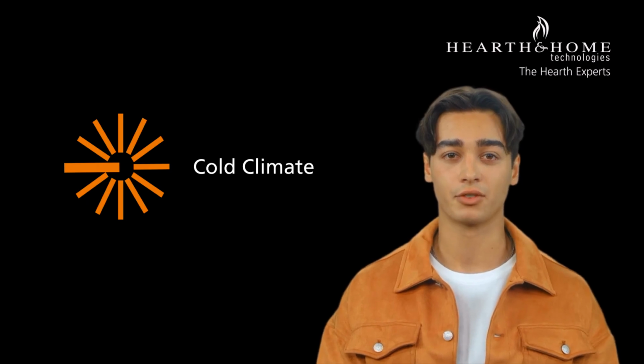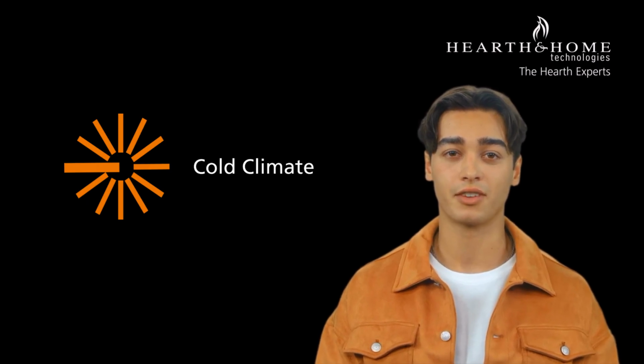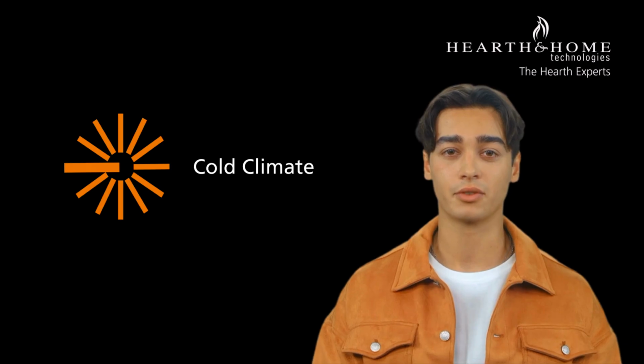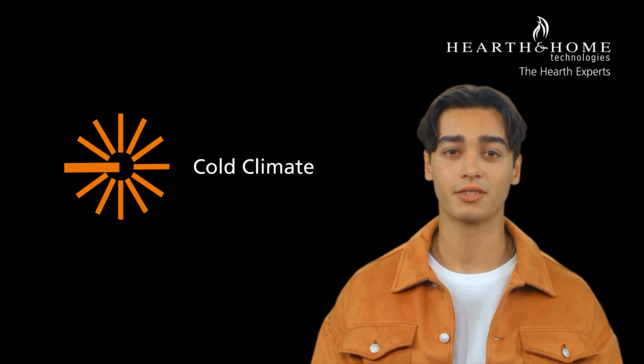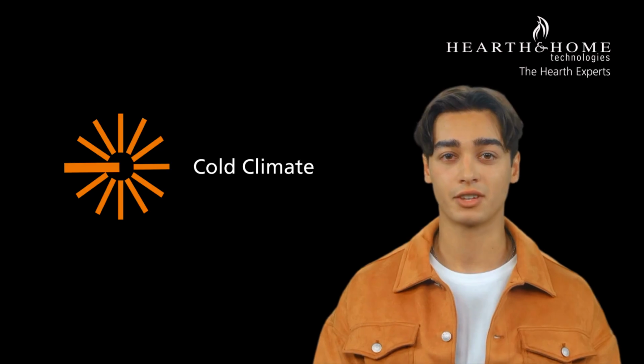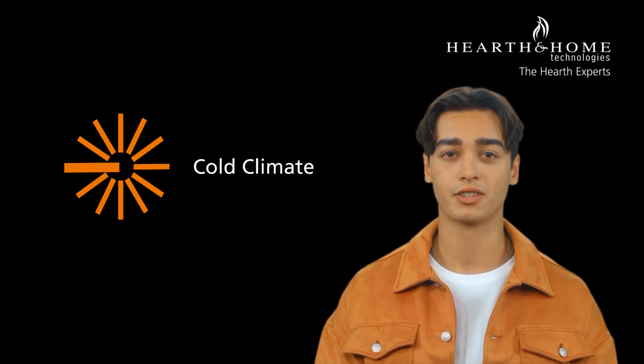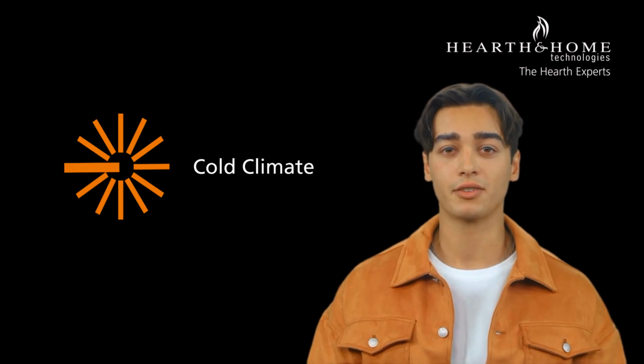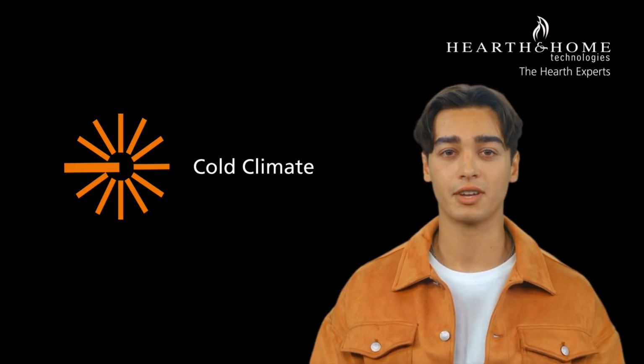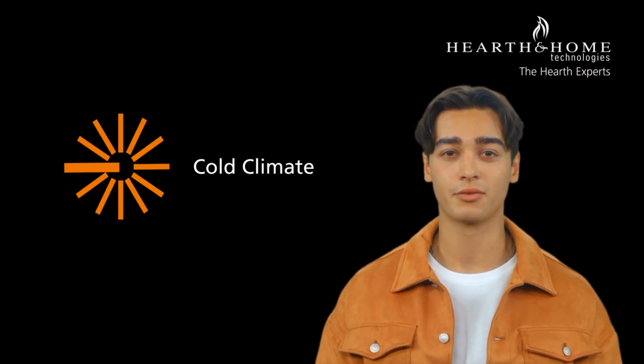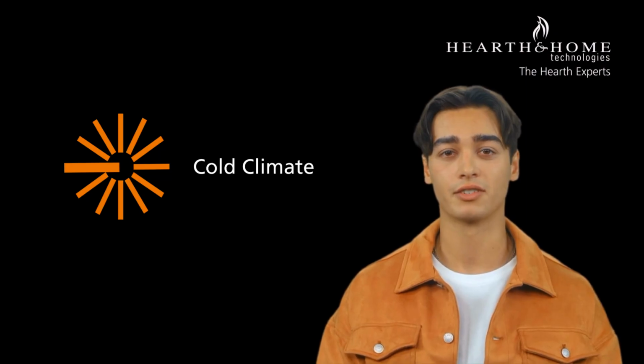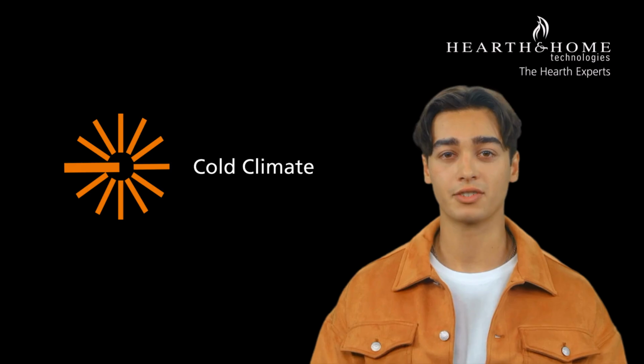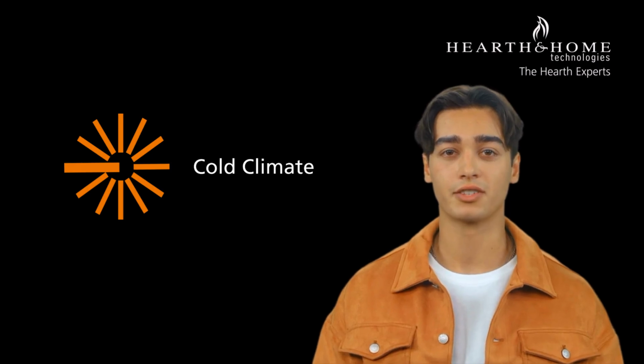At the highest level, cold climate is a non-permanent pilot flame in your fireplace. Let's break that down even further. Non-permanent in this case means it will not run forever. A standing pilot was a common thing in gas fireplaces of the previous generations. This meant the pilot flame or pilot light stayed on forever. Cold climate, on the other hand, will run for 6.9 days without any use of the fireplace before shutting down. Because our products are sold throughout the US and the world, we had to enforce this specific time on cold climate in order to meet certain local or state regulations.